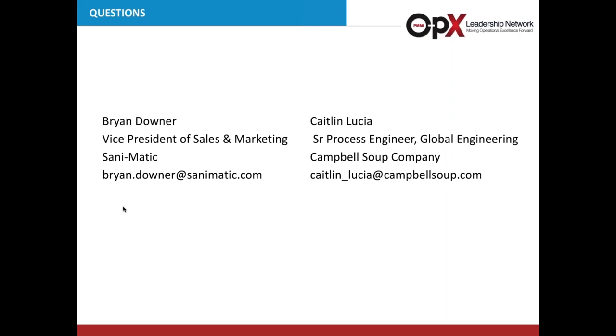Caitlin, how do I retrofit my process systems for CIP? Since designing for CIP is key for having a CIP-able system, you can't often snap your fingers to retrofit it. Start with the available standards and audit your existing process against those — are the components CIP-able? Do I have the right installation as Brian covered — no dead legs, good welds? Then start tackling them one by one until you have something equivalent to what you would have designed from scratch. You can also do riboflavin testing to check your vessels if they weren't originally designed for CIP.